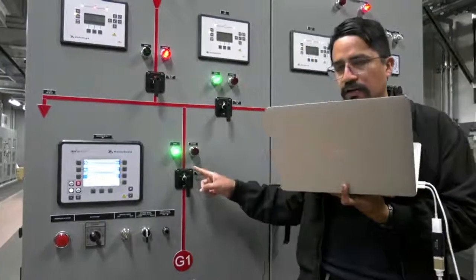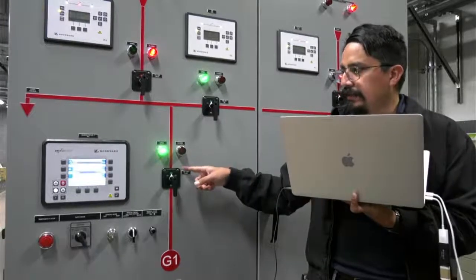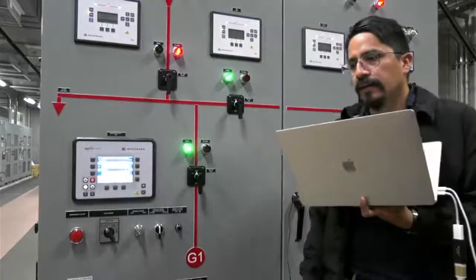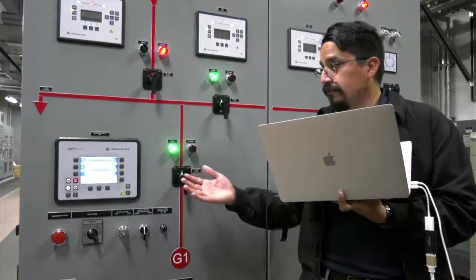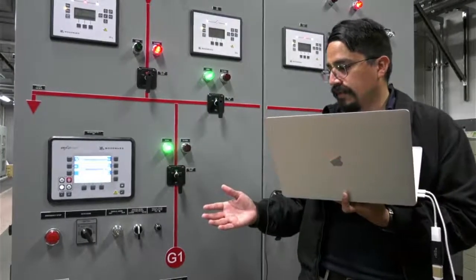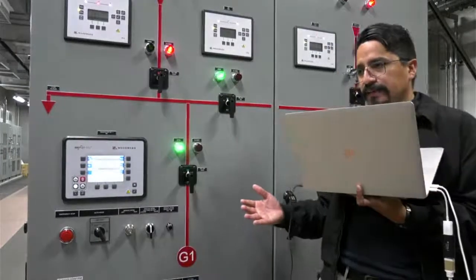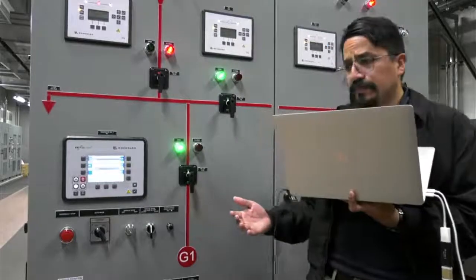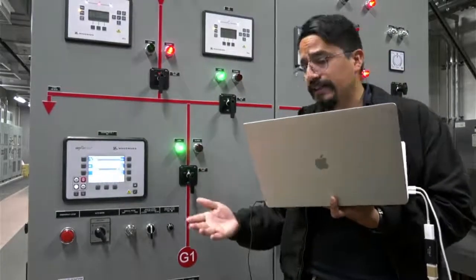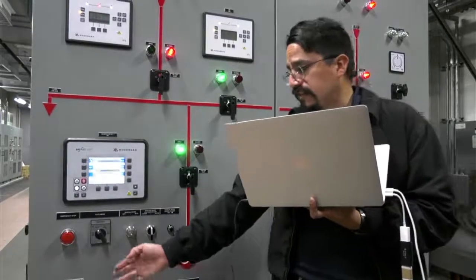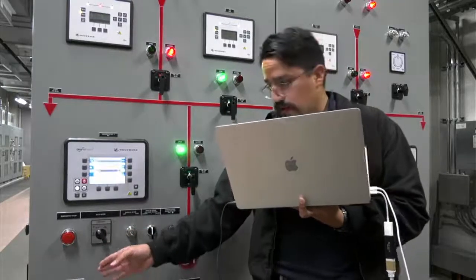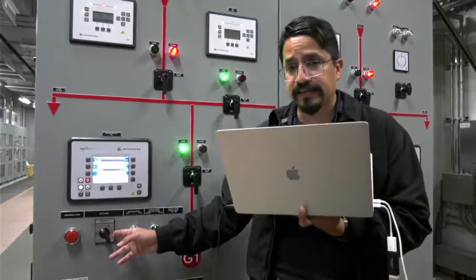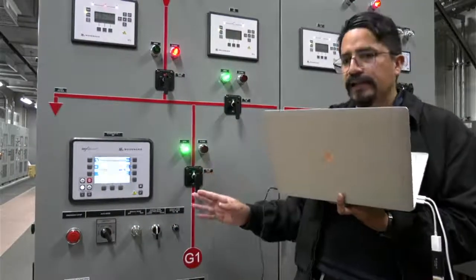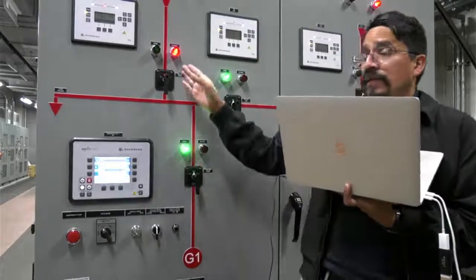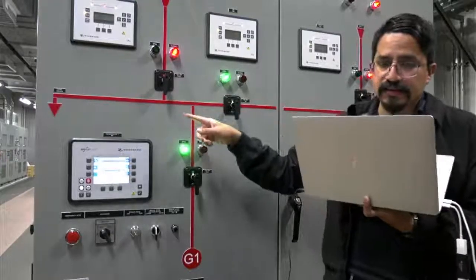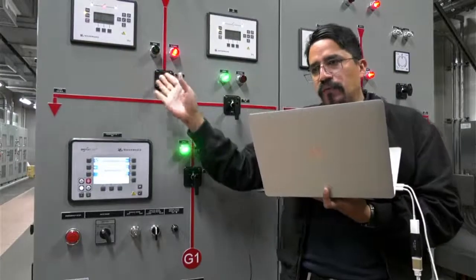Once it's stable, it's gonna close the circuit breaker and it's gonna energize all of this area. But this means that you are gonna go to blackout. This is not desired, and this is just for testing the functionalities. In this situation, it's recommended to, instead of doing a field test, do an online test. With the system in auto, you go and select your online test, and it's not gonna do a blackout. The online test is gonna run the engine with the main breaker closed. It's gonna synchronize, close, and then open the TICO, so the load is not gonna be off.